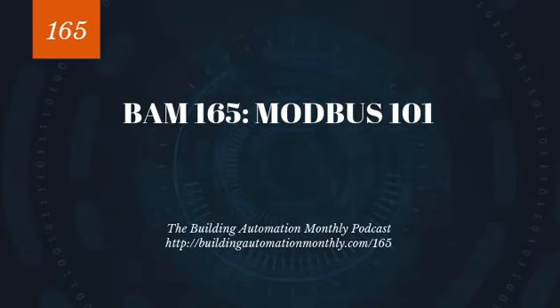Now, there are two stacks when we're utilizing Modbus. We're utilizing TCP/IP or we're utilizing RS-232 and RS-485. And actually, the versions of Modbus that do this are quite different. You have Modbus TCP, or Transmission Control Protocol, which utilizes IP addressing and uses TCP for the connections between the clients and servers. And then you have Modbus RTU, right? And RTU is using RS-485 and RS-232. So there's a big difference between these two. It's something we dive into in great detail in our course.